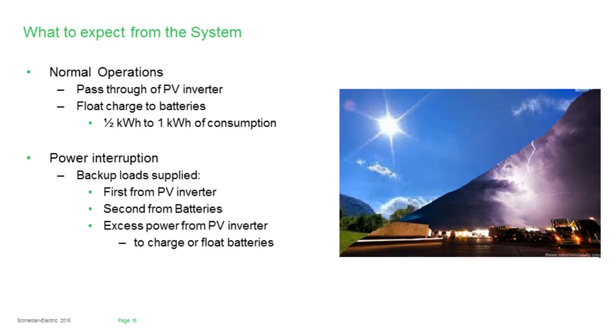Hopefully there's a nice balance, so whatever the system consumes—let's say we have a two-day power outage, and throughout the evening the system consumes power, and by the next morning the batteries are low—we have enough extra PV to actually charge the batteries while covering the loads inside the home. So when figuring out how much PV to put into the system, we need to size for daytime loads and also size to cover some charging into those batteries, all while making sure we don't accidentally overcharge them by pushing too much current onto them.